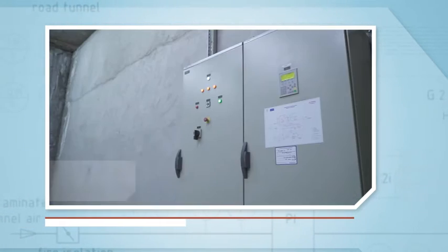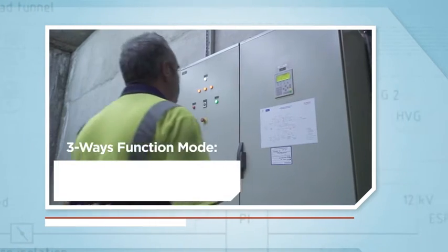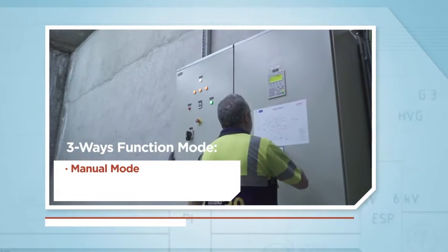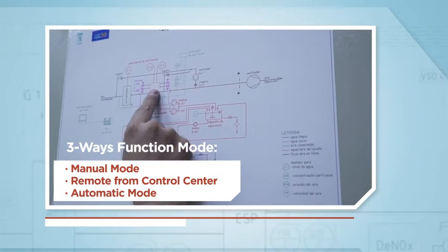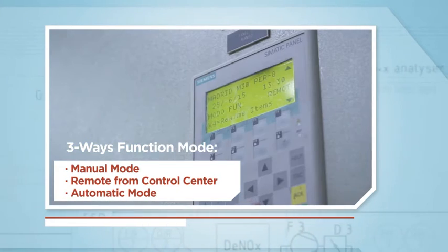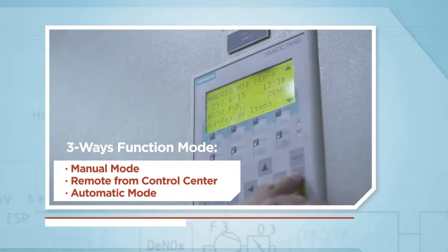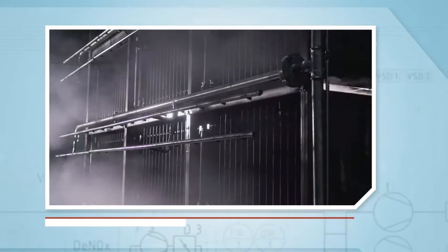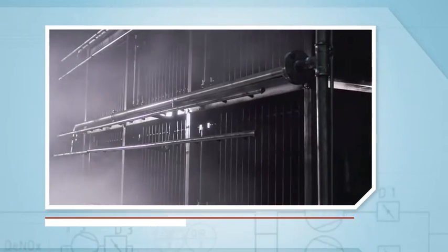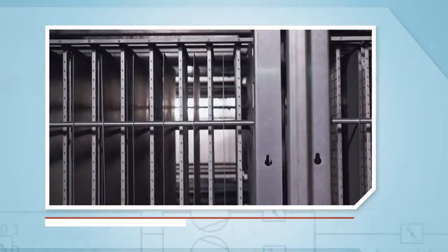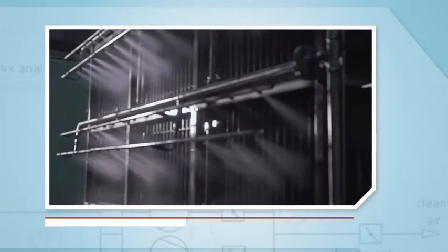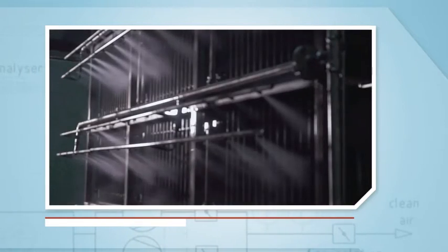After the washing, the totally automatic system moves on to a drying or air blowing sequence using compressed air, which makes it possible to significantly reduce the drying time and so reactivate the filter availability in less than 30 minutes.